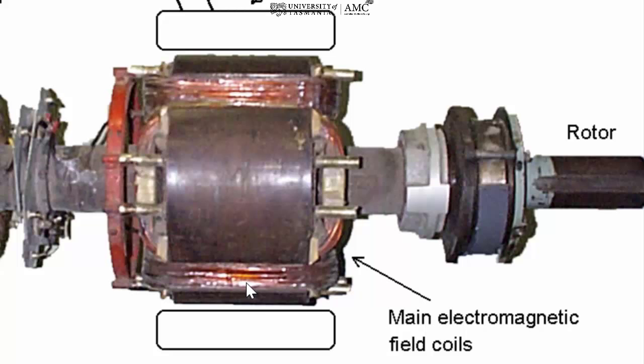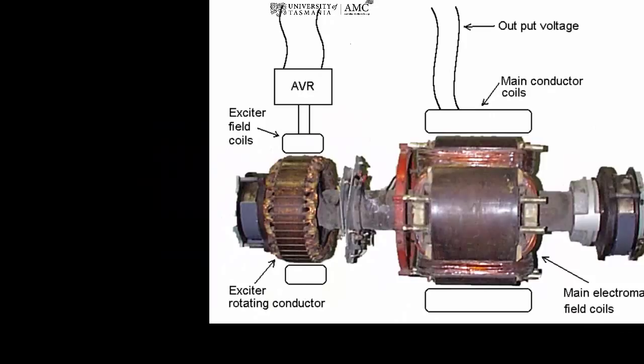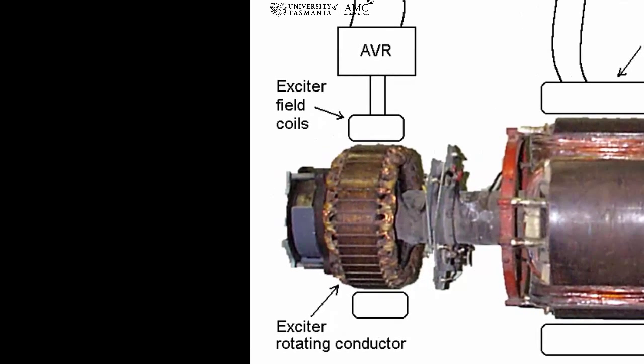So this one's a 4-pole alternator on one shaft, our rotor, and the wiring to supply the DC voltage to our field coils comes through along the rotor, and then our conductor coils are there in the stator on the outside, and our output is from here. Our output is also sensed by our AVR, the automatic voltage regulator. So that senses part of the output, and it goes through a comparator, and then our exciter is wired exactly the opposite to the alternator.